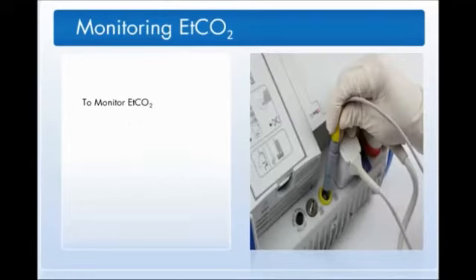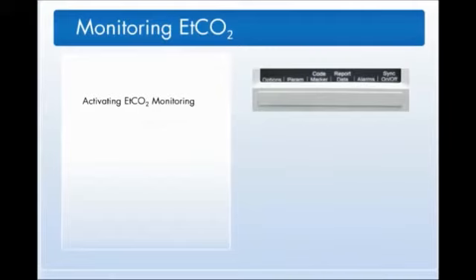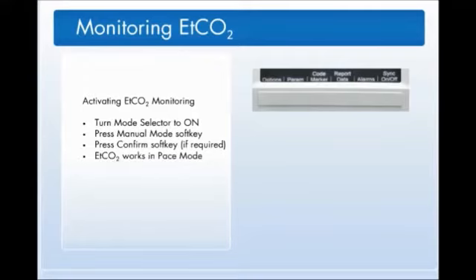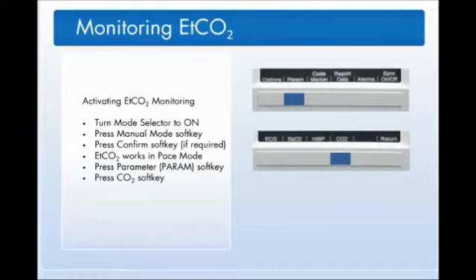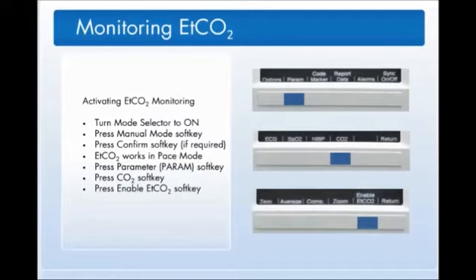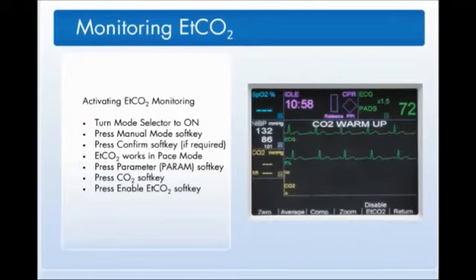To begin EtCO2 monitoring, plug the EtCO2 cable into the back of the R series in the yellow port marked CO2. Turn the R Series Plus to On and select Manual Mode or Pace Mode. Press the Param soft key. Then press the CO2 soft key. Then press the Enable EtCO2 soft key. The message CO2 Warm-Up will be displayed. This will take approximately 60 seconds.